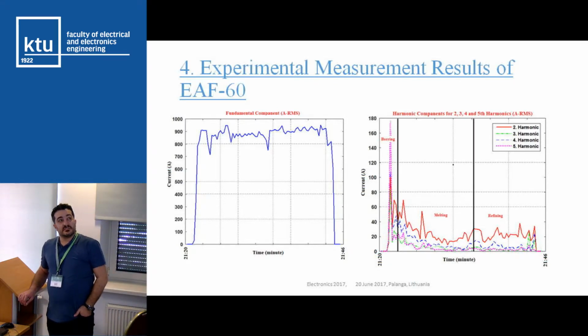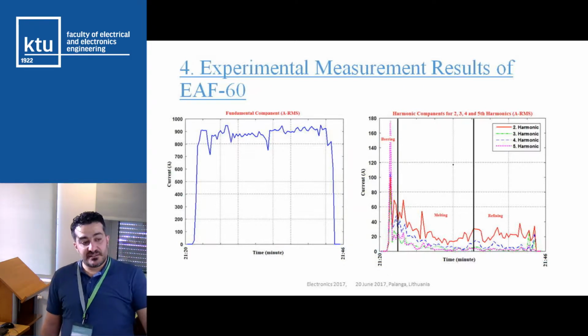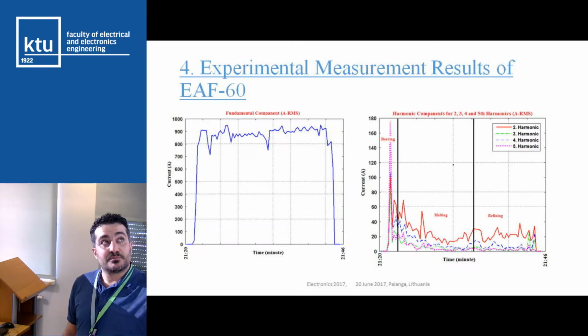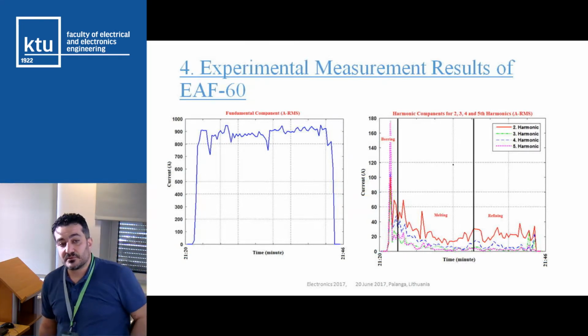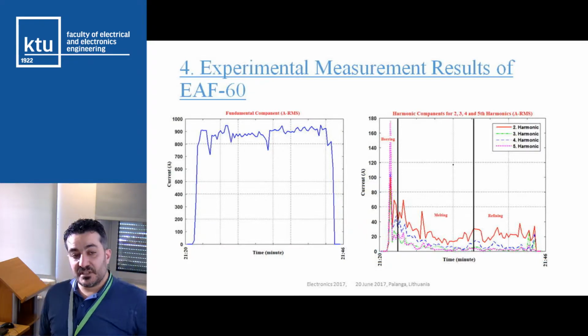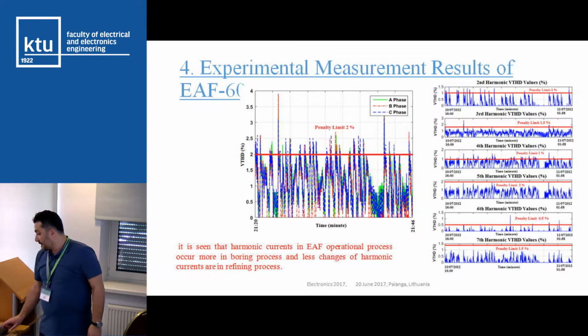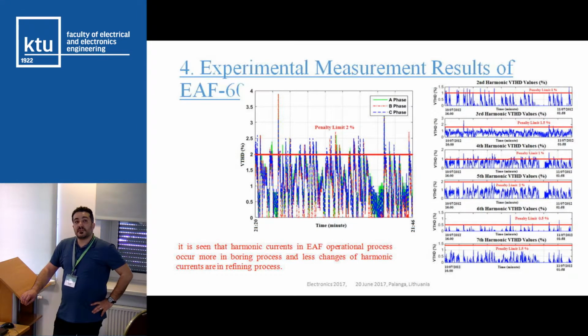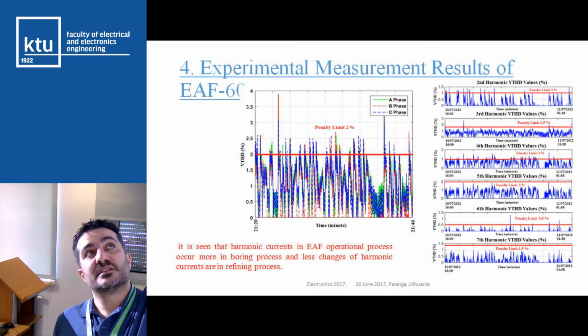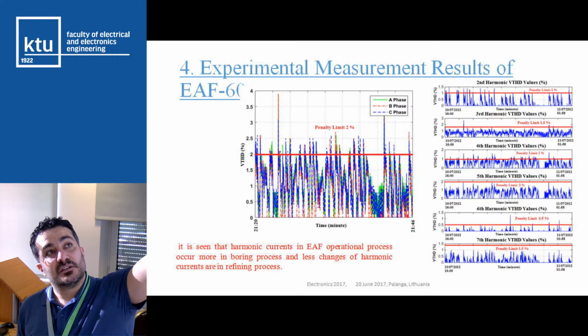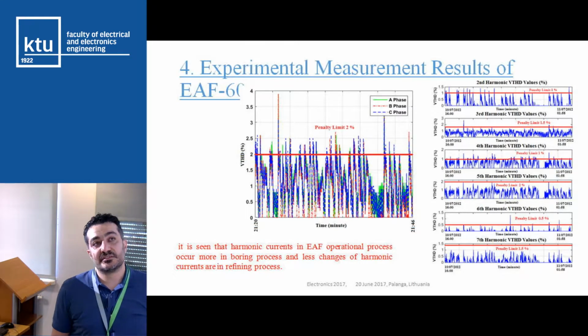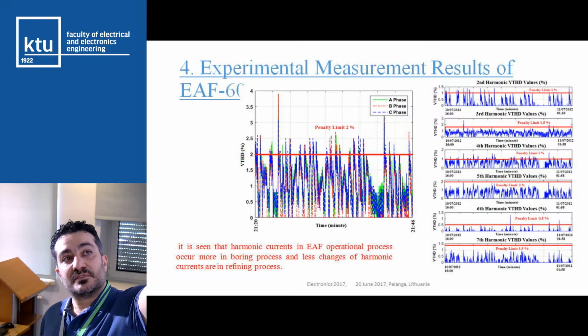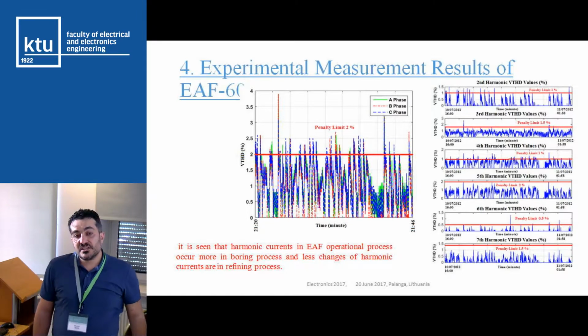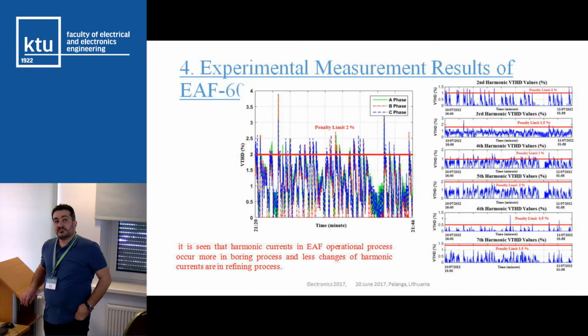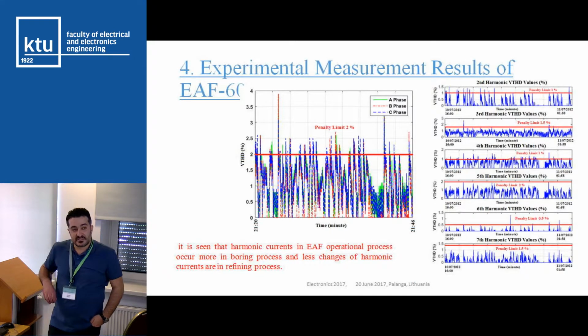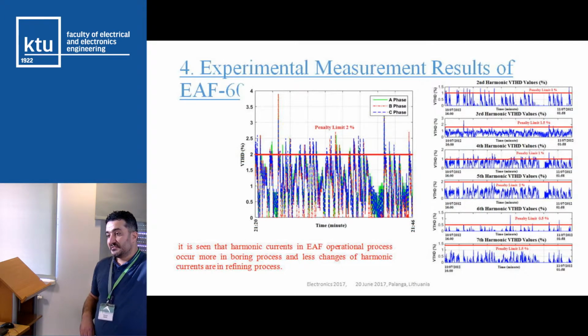When we look at the experimental results, especially in the melting process and especially in the charge and boring process, we can see that harmonic values are very high, and in the refining process we can see a stable manner. When we look at the harmonic values, the second harmonic is bigger than standards, the third harmonic is sometimes bigger than standards, and the fourth harmonic is bigger than standards. Generally, we can see that even harmonics and odd harmonics are bigger than standards, and total harmonic distortion is always bigger than standards.